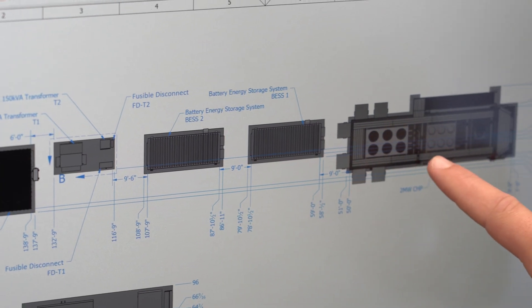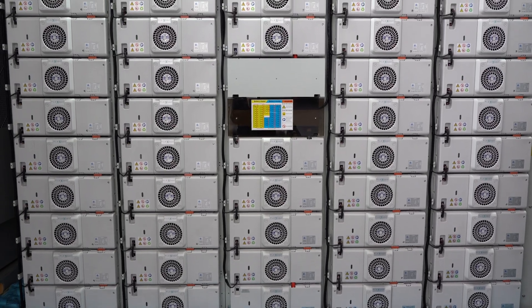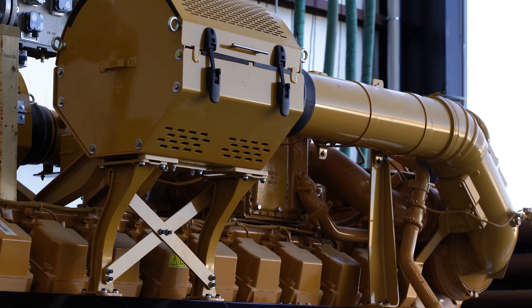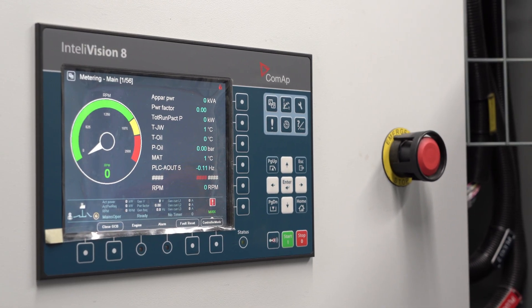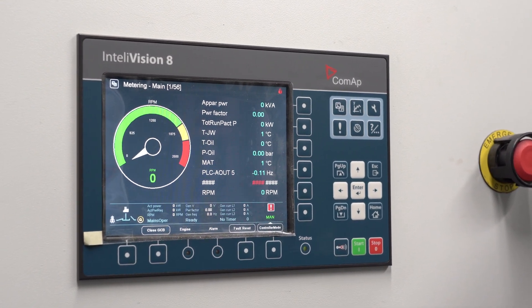We recently completed a project that is a microgrid providing power for a local subdivision in New York. The point of it is to provide backup power in the event that the utility would go down. We are doing that by installing a battery energy storage system and a natural gas genset that will work together. All three of these power sources tie together in the switchgear and then distribute power to the subdivision. We also installed a ComAp microgrid control system on top of all that, which ultimately dictates which power source is supplying power.